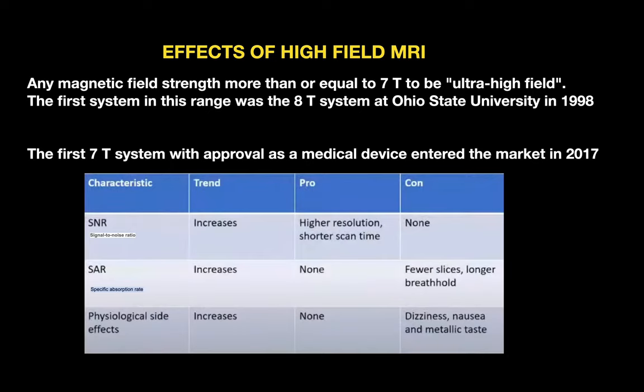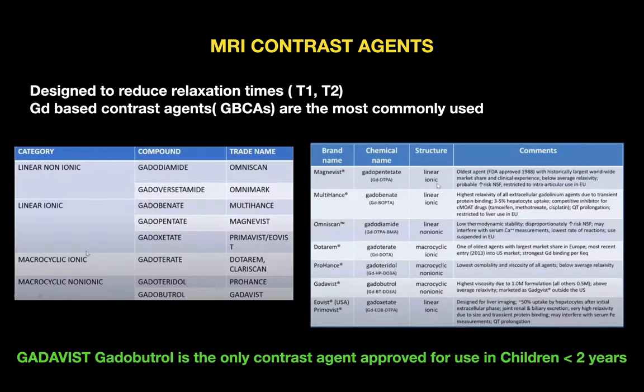Regarding ultra-high field MRI: any magnetic field strength of 7 tesla or more is called ultra-high field. The first system in this range was an 8-tesla system at Ohio State University in 1998; the first 7-tesla system with approval as a medical device entered the market in 2017. Effects include increased signal-to-noise ratio, increased specific absorption rate, and increased physiological side effects like dizziness, nausea, and metallic taste. However, it provides high-resolution scans with very short scanning times.